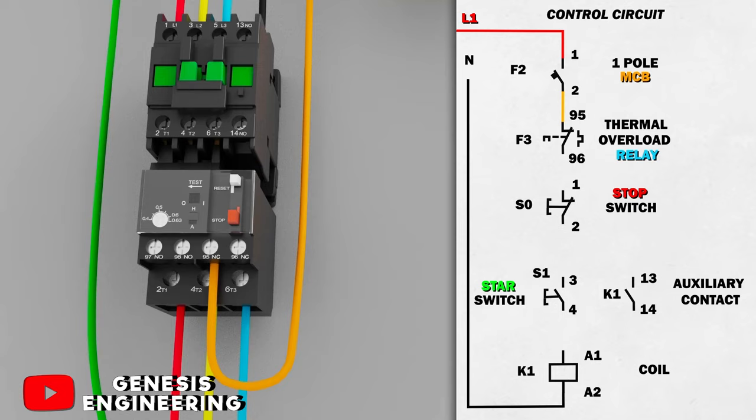We are connecting first to the normally closed contact 95 and 96 of the thermal relay because we are making a series connection with the contactor coil. In the event of an overload in the motor, the relay will open contact 95 and 96 and will interrupt the power supply to the contactor coil, and the contactor will shut off the motor.